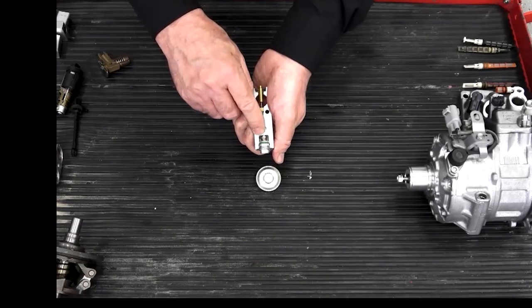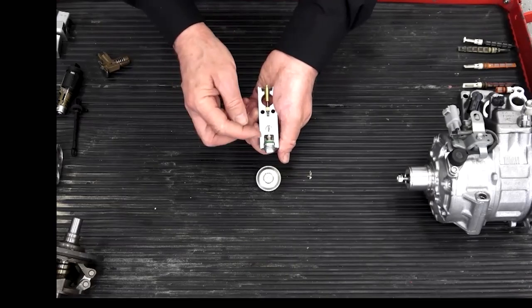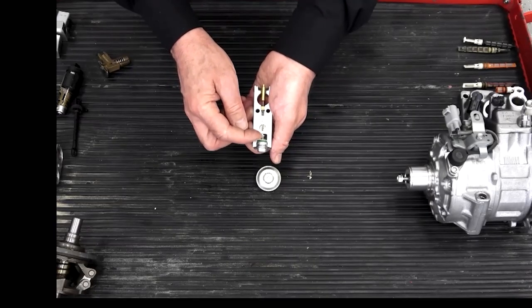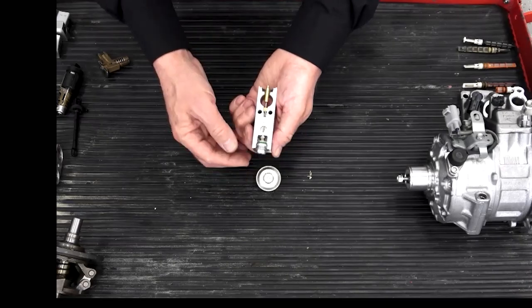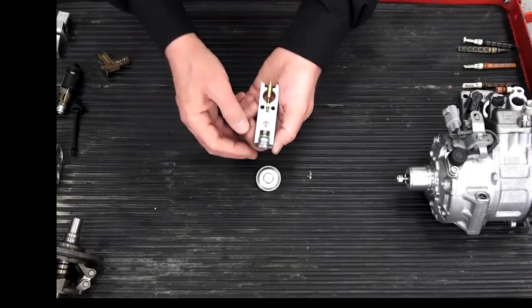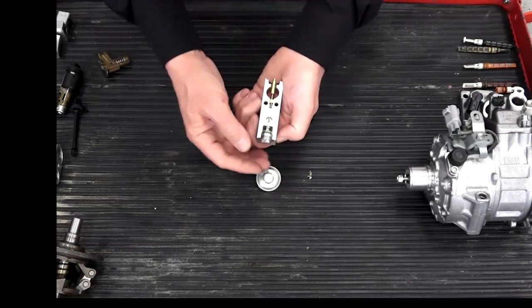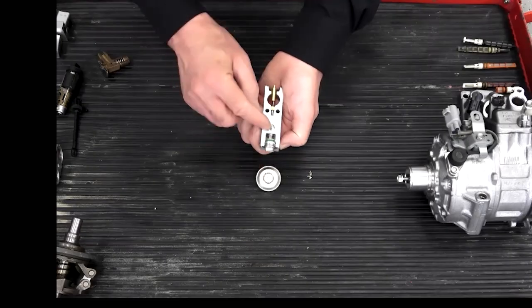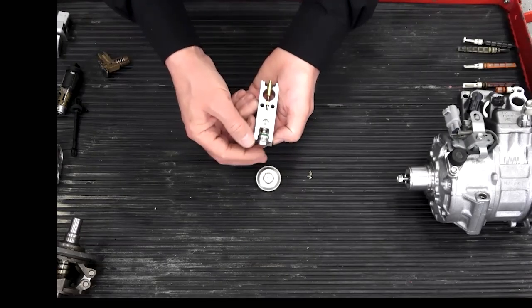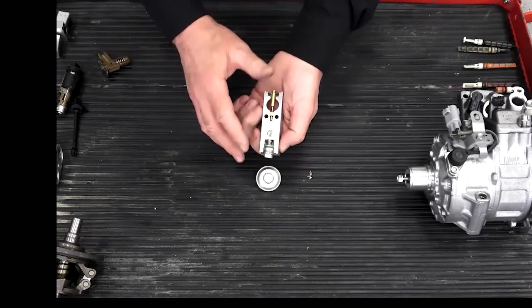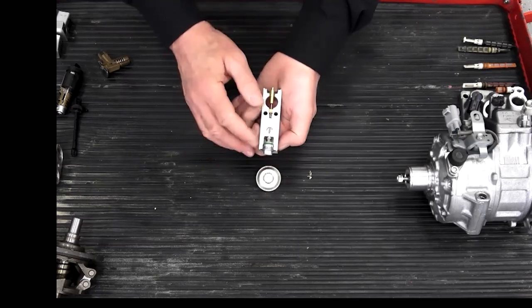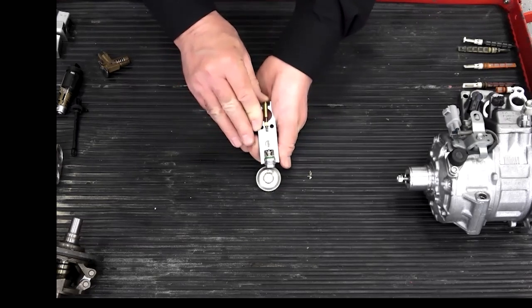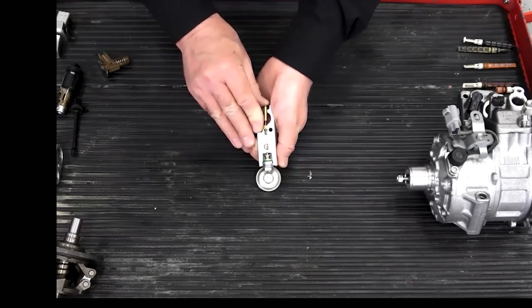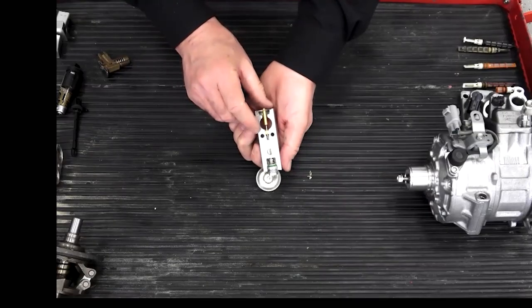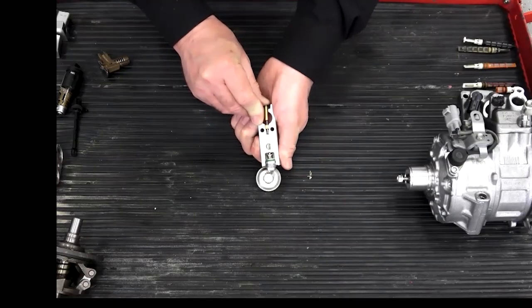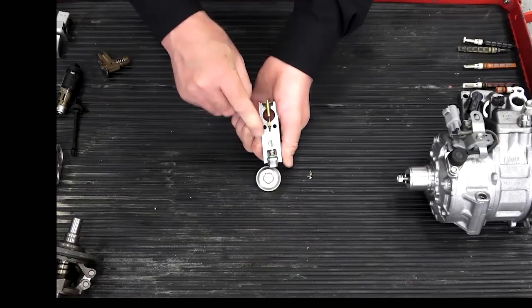Now, you notice that the ball valve is spring-loaded closed. This is the superheat spring here. I do want to caution you, you do not want to mess with this. It can be removed, that's just for assembly purposes. You do not want to mess with the superheat screw here. This is all set up in a laboratory environment at the factory. You do not want to mess with this in the field. So the way this works is this.